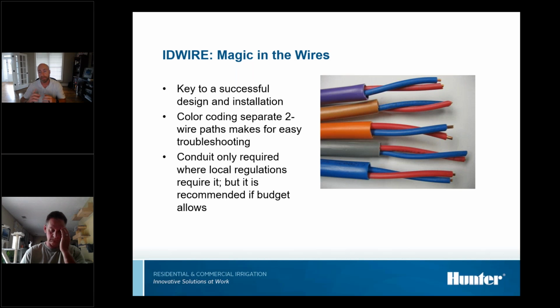But I will say, if the project budget allows for it, it's a good thing to have. I've seen projects where the 2-wire path was put in conduit, and then something happened, like a road being built, that broke it, causing issues on the 2-wire path. Since they had conduit there, they were able to replace the entire 2-wire path between each valve by just pulling out the old and pulling in the new at the same time. So it gives you flexibility and protects the wire, but it's not really required. A lot of times, if it does get installed, it ends up getting value engineered out. But if the project has the budget for it, I'd definitely recommend it, though it's by no means required.